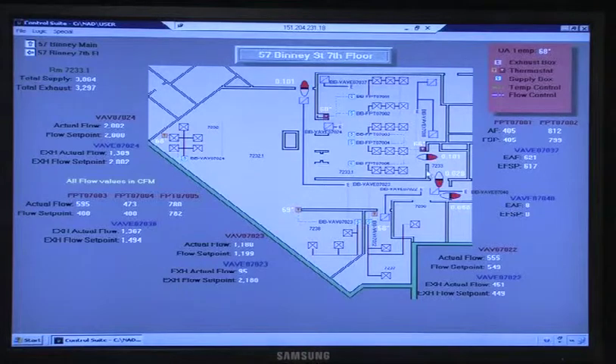Right. So we won't be able to disable those pressure alarms, those are gonna always be active. No, we'll have to have a delay on them. Yes, an adjustable delay for us. Just wanna let you know, the wires are still sitting there waiting for those door switches, we just couldn't figure out a way to do it physically. Yeah, I don't think it'll be much of an issue, because those doors are always closed.